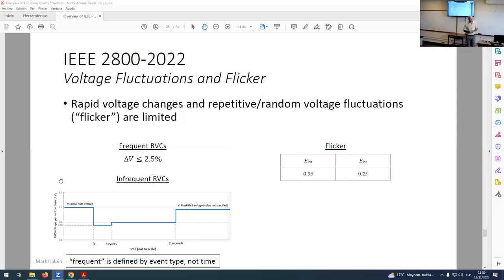As far as voltage fluctuations and flicker are concerned, well, the traditional PST flicker limits in 2800 are the same as they were in 1547. Short-term flicker severity of 0.35, long-term flicker severity of 0.25. Should it be that? No. No way. But that's what it is. Okay? There's a lot of reasons why it is that way in this document. It's very difficult to make a standard that gives one number. And so these are very, very conservative values, okay?